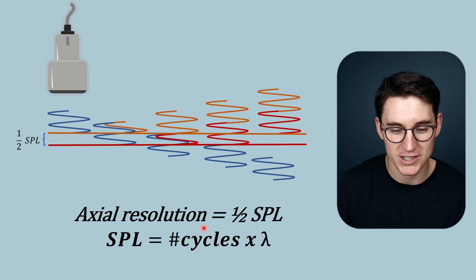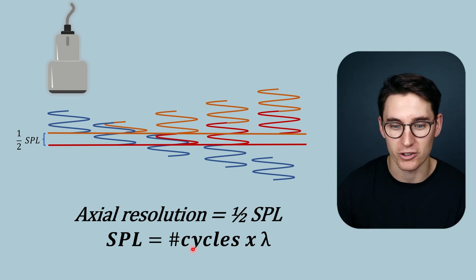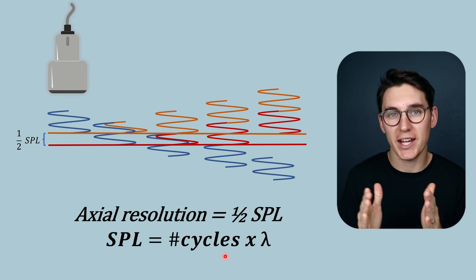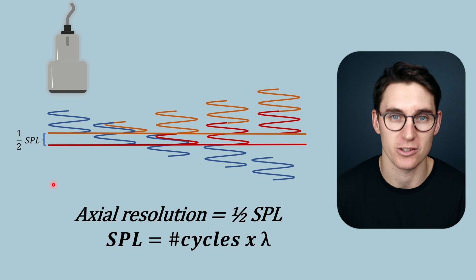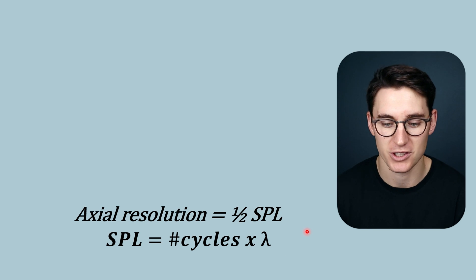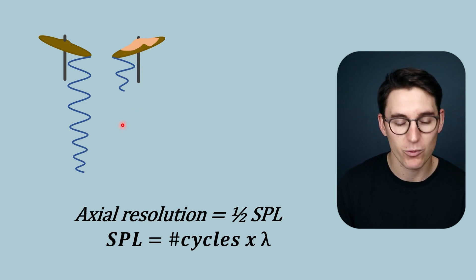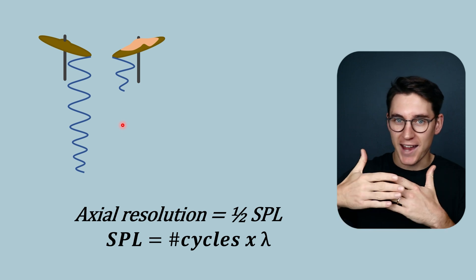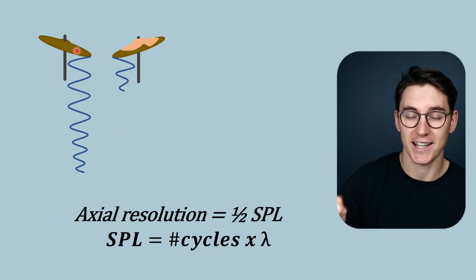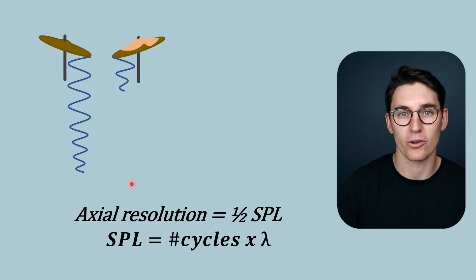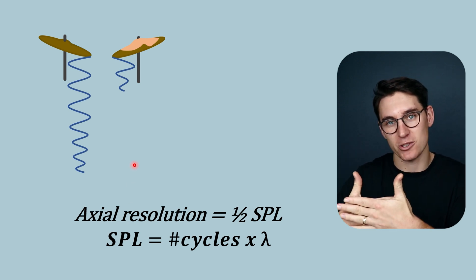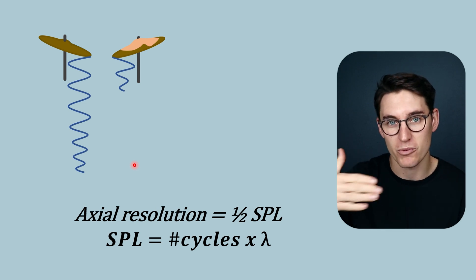Our spatial pulse length is determined by the number of cycles within the pulse as well as the wavelength of that pulse. There are various factors we can change to alter the spatial pulse length and ultimately the axial resolution. The first is changing the number of cycles within the ultrasound pulse. When we looked at creating an ultrasound pulse, we looked at dampening: if we fire a piezoelectric crystal and let it resonate at a set frequency, like hitting a cymbal, that crystal will ring for a long time releasing ultrasound pulses into the tissue.